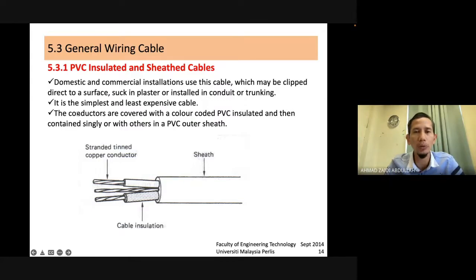And then the conductors are covered by colour-coded PVC insulation, and contain single or several cores in a PVC outer sheath. This makes marking and so on easy for us. That's why JKR also agrees to use it for standard wiring. So we use PVC with colour. For example, for 3 phase, they apply red, yellow and blue cable using PVC cable, and for earthing green colour and neutral black colour.